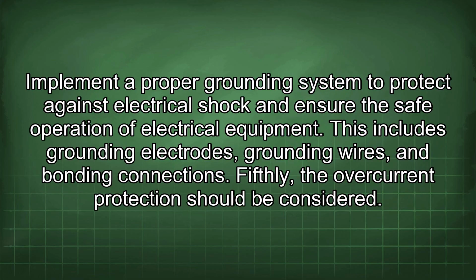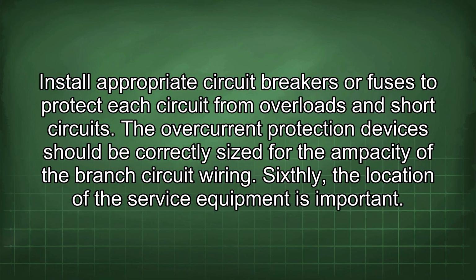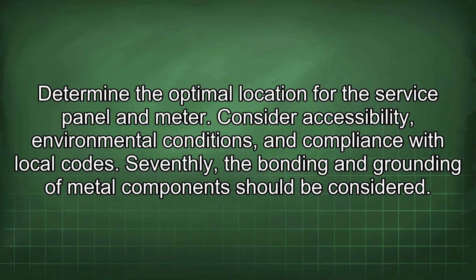Fifthly, the overcurrent protection should be considered. Install appropriate circuit breakers or fuses to protect each circuit from overloads and short circuits. The overcurrent protection devices should be correctly sized for the ampacity of the branch circuit wiring. Sixthly, the location of the service equipment is important. Determine the optimal location for the service panel and meter. Consider accessibility, environmental conditions, and compliance with local codes.